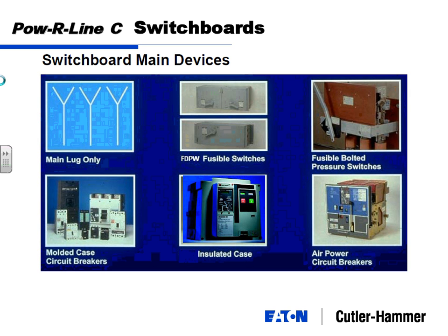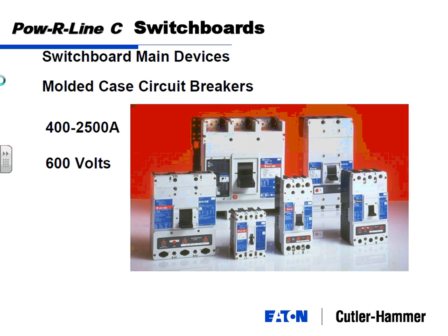So for the main devices, just like panel boards, we had main lugs only, fusible switches, or molded case breakers. Because we've gone higher in ampacity, with fusible switches we've got a new kind called a bolted pressure switch. A normal fusible switch goes up to 1200 amps. A bolted pressure switch goes up to 4000 amps. The bolted pressure switch just takes a lot more beef, a lot more pressure, to hold things together at that amperage. And two other classifications of circuit breakers are an insulated case or an air power circuit breaker. Molded case breakers go up to 2,500 amps. So a molded case breaker, the biggest one might be, say, the width of this computer and maybe 20 inches high. That'd be a 2,500 amp one.